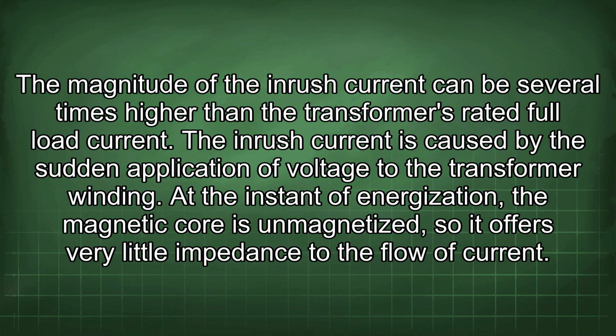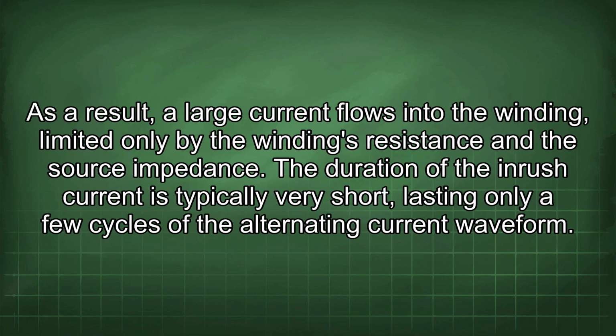At the instant of energization, the magnetic core is unmagnetized, so it offers very little impedance to the flow of current. As a result, a large current flows into the winding, limited only by the winding's resistance and the source impedance. The duration of the inrush current is typically very short, lasting only a few cycles of the alternating current waveform.